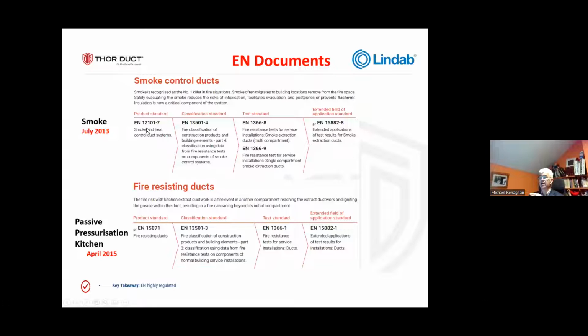The standards are all EN 12101-7, 15871. Don't worry about the numbers. They're in the booklet. So you can go and see this little chart inside the booklet. You'll always have the numbers. So we have a product standard, classification standard, test standards, and extended field of application. The product standard is the overall global. The classification standard determines how you report your results. So you have 10 different suppliers with 10 different testing regimes, but the classification report levels the playing field. So it tells you how they've performed. Very important document.